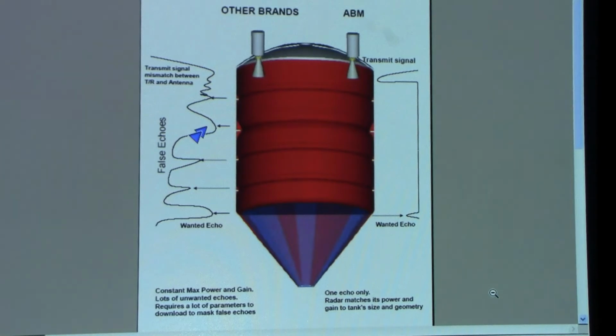The other brands, as you can see in this picture, offer maximum gain, maximum transmit power, and fixed transmit pulse length. As a result, we receive a lot of false echoes from the tank's wall. These false echoes have to be processed to obtain the wanted echoes from a liquid or solid level. The processing of false echoes is very difficult, and in many cases it doesn't work.